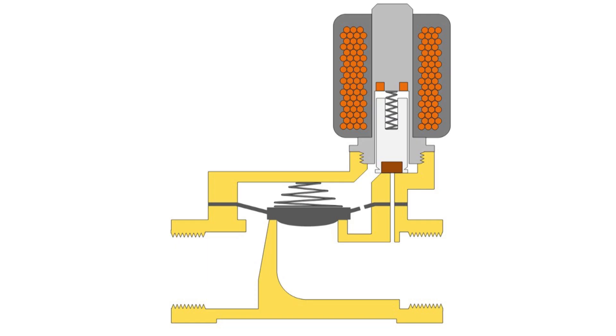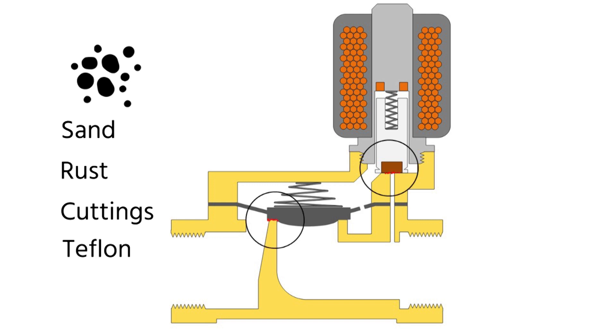Solenoid valves are very sensitive to dirt particles in the fluid. If you have a problem with a leaking solenoid valve, the reason is usually due to small particles of sand, rust, cuttings, or pieces of Teflon tape on the valve seat or in orifices.